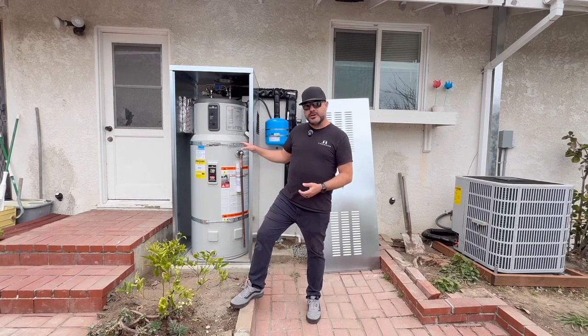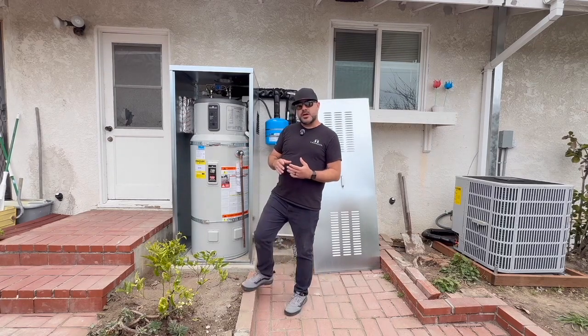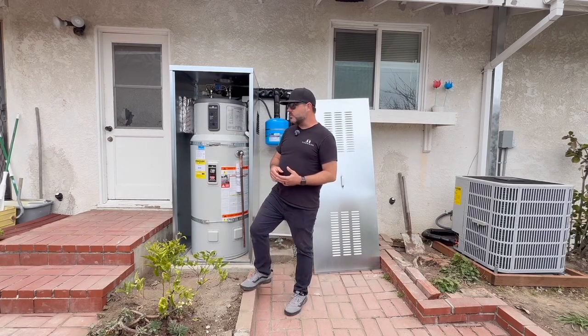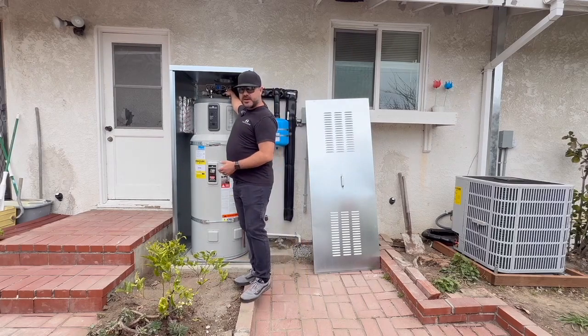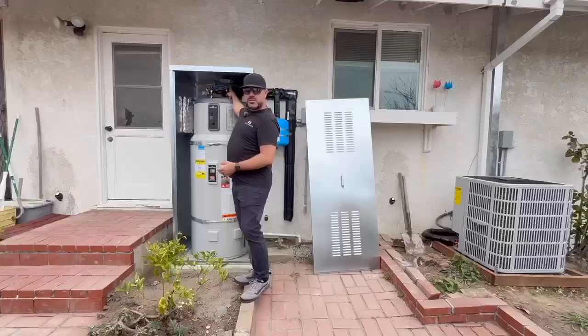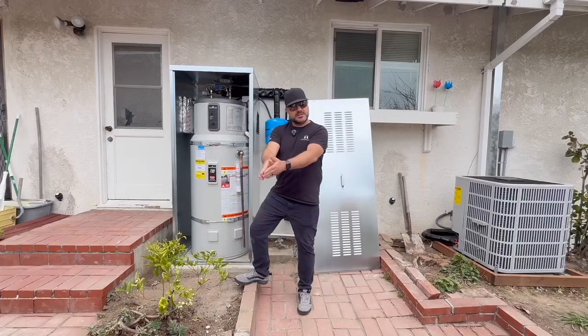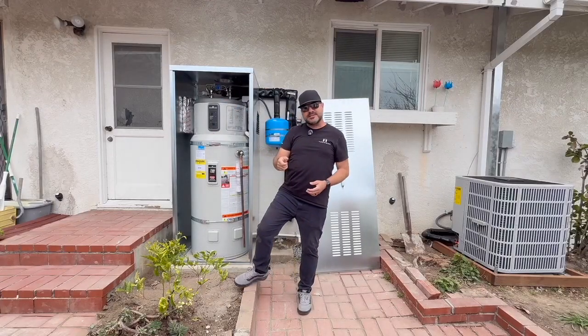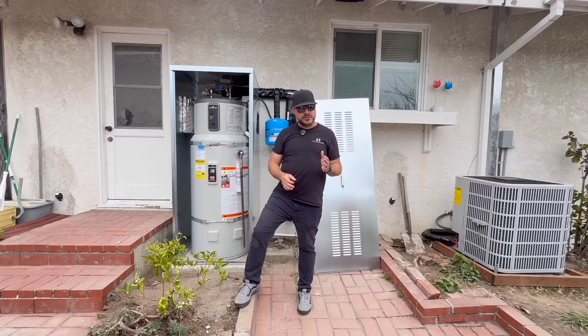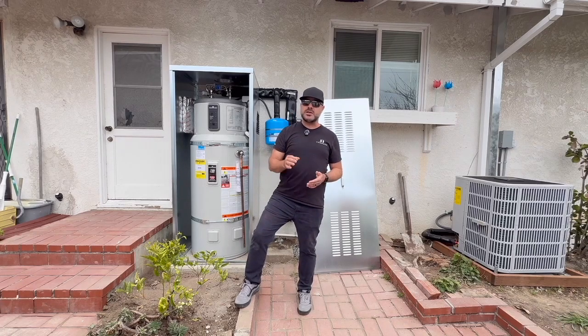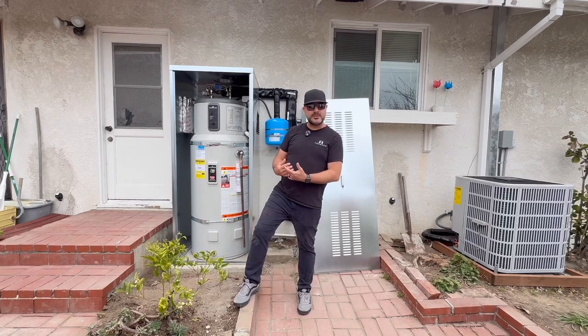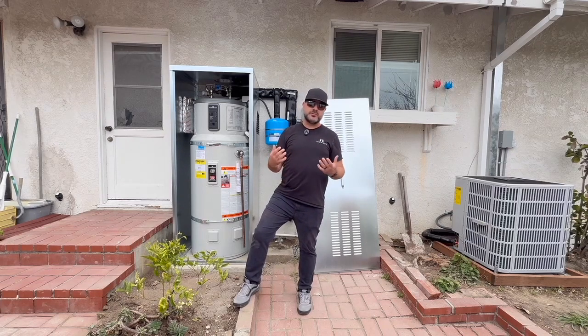We're going to store water here at 140 degrees. To prevent us from distributing 140 degrees into the home, we install what's called a mixing valve. This actually mixes water from the cold side into the hot side as it's distributed into the pipes. We balance that very precisely so you get 120 to 125 degrees going into your home, which is the appropriate safe temperature of water to deliver into the house, not only for us, but also for your fixtures and piping.